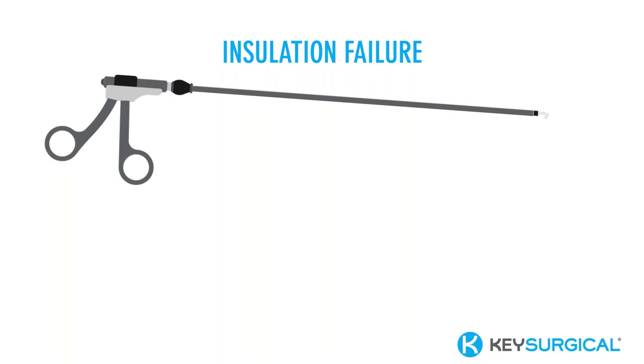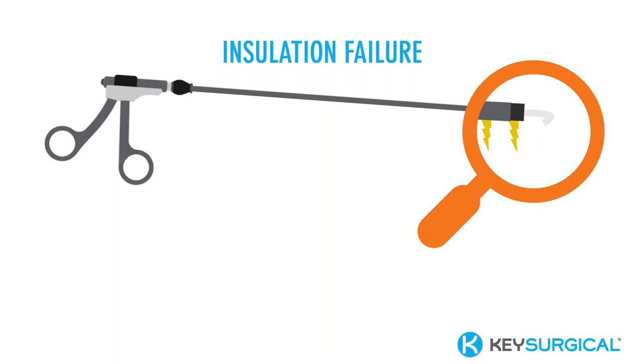So they tested 226 instruments, a mix of reusable and disposable. And what they found, as we might expect, is that reusable instruments had a greater frequency of insulation damage than disposable instruments. That was about 19% in reusable instruments compared to 3% in disposable. The second thing they found is that insulation damage was most common in the distal, the farthest away, distal 3rd tip. That's the end that we have magnified here. The reason we like to cover this is that when we know this information, we know those places to focus on or monitor and watch.